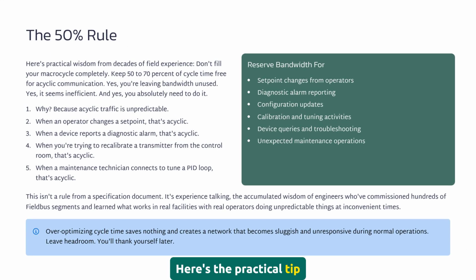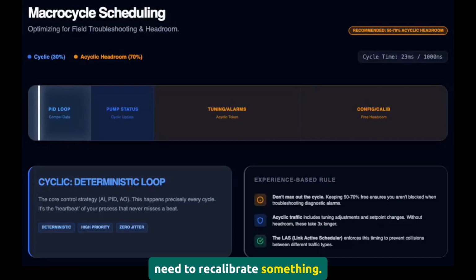Here's the practical tip I've learned the hard way. Don't fill your cycle up completely. Keep 50 to 70% of your cycle time free for acyclic communication. Why? Because real fieldwork isn't predictable. You're going to need to change a set point. A diagnostic alarm is going to fire. And you need more information. You're going to need to recalibrate something.